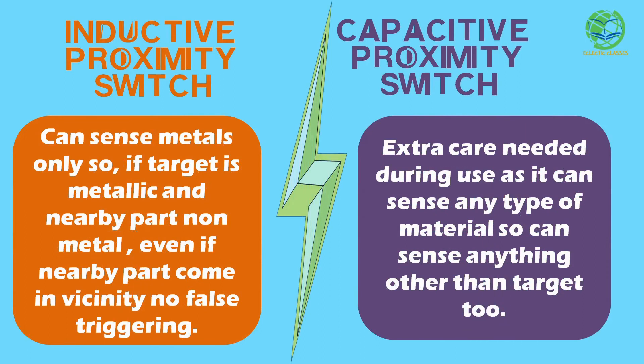Capacitive sensors' installation and use need extra care, as they can sense any type of material. During operation, it must be ensured that only the target object comes in the vicinity of the sensor. If any other part also comes near the sensor, it will treat it as the target and start triggering. In case of inductive sensors, we need not worry as much, since they can sense only metals — so even if nearby non-metal parts come in the vicinity of the sensor, it won't false trigger.